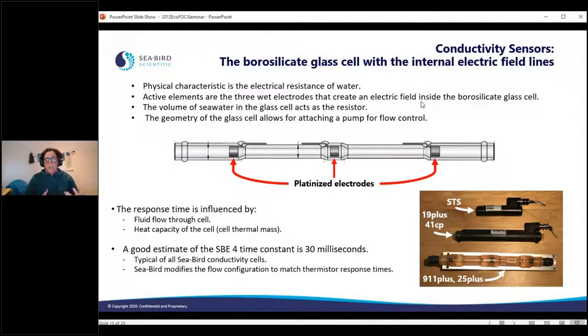You need the conductivity sensor to get the salinity of seawater. It's essentially just a glass tube that measures the electrical resistance of the water. Using the temperature, pressure, and a long equation, you figure out the salinity. This is really one of Seabird's main technologies—this conductivity sensor has three platinized electrodes creating an electric field, and with all the seawater in that tube, you measure the conductivity and get the salinity. That's how you get really, really accurate results.